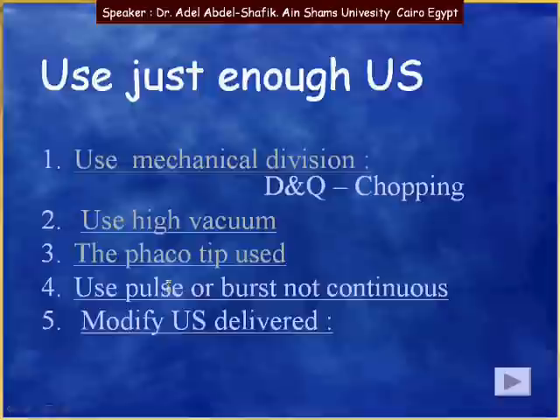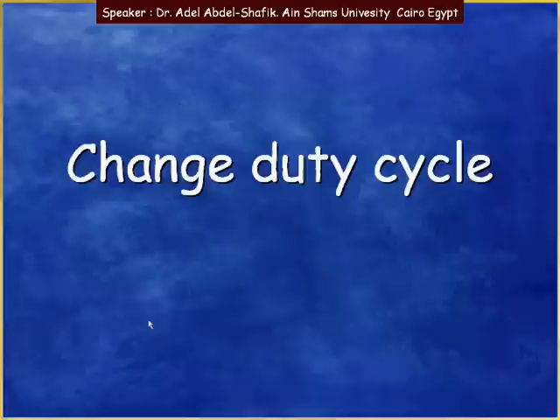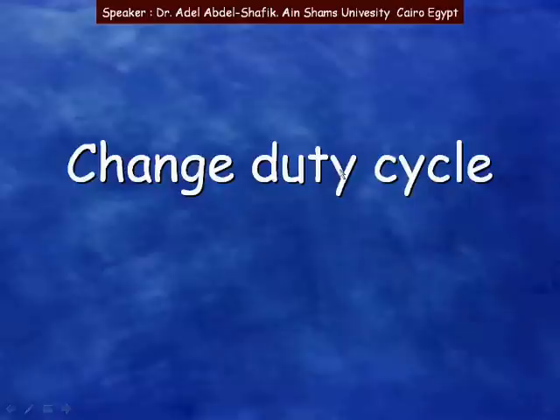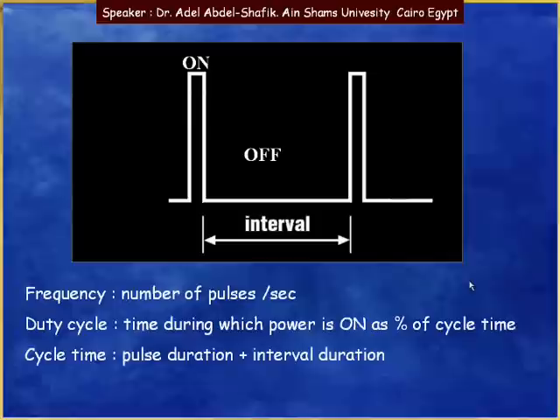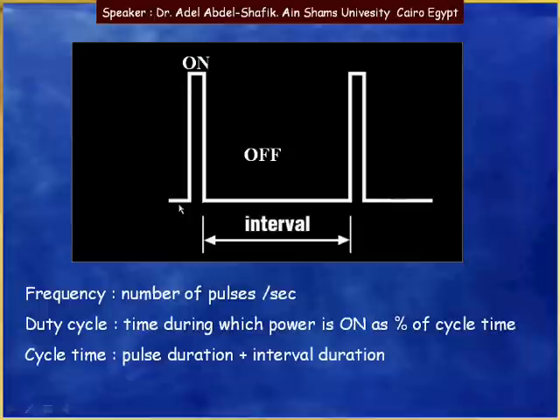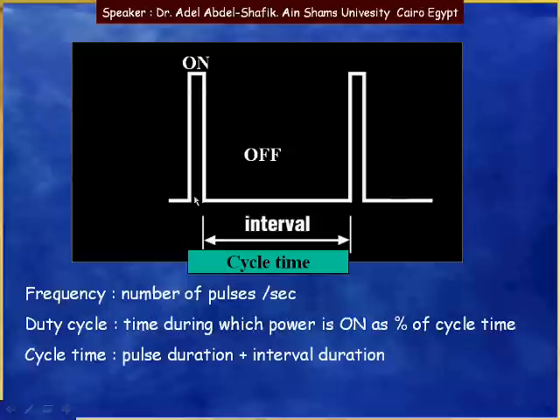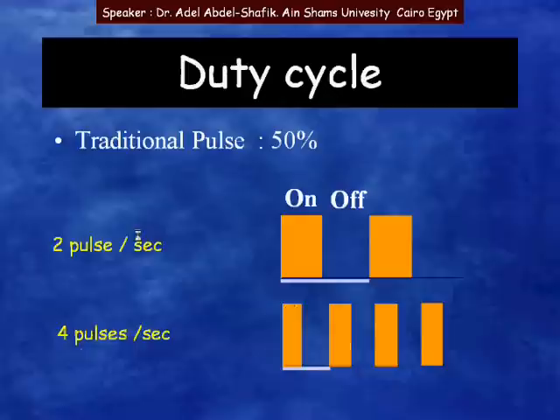We can also use pulses or bursts rather than continuous ultrasound, which delivers less total energy. Lastly, we can modify the ultrasound by changing the duty cycle. The frequency means the number of pulses per second. The duty cycle is the time during which power is on, expressed as a percentage of the cycle time. The cycle time is the duration of a pulse plus the duration of the interval between one pulse and the next — the on part and the off part together.